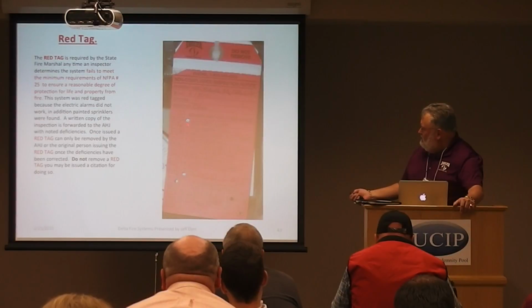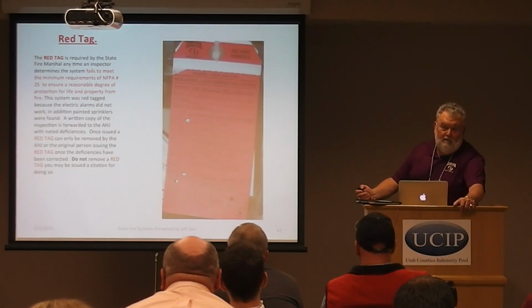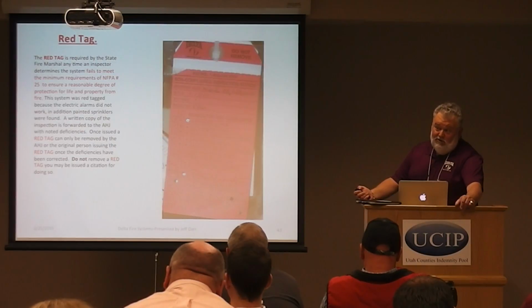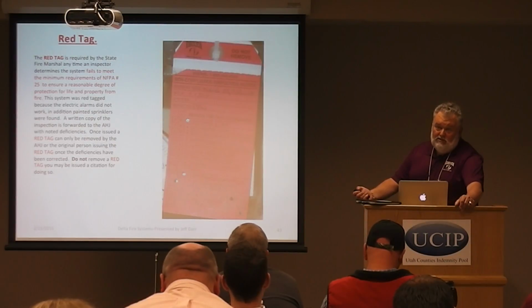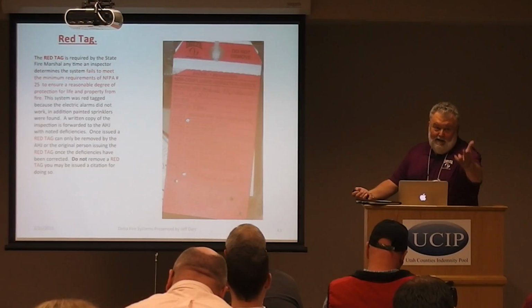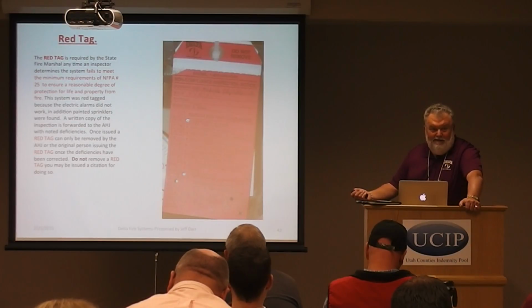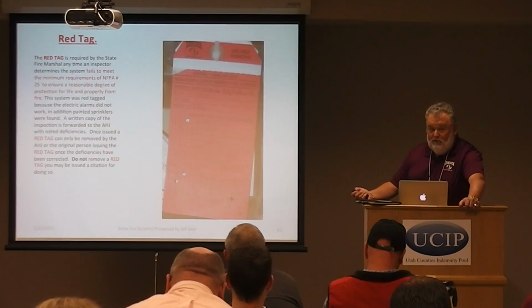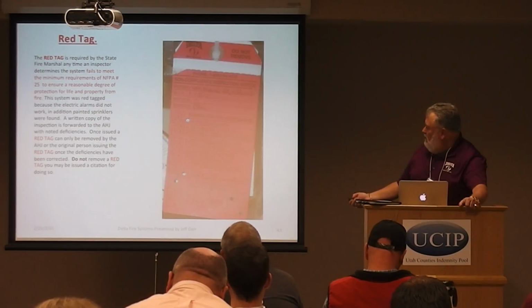This system here was actually red tagged. I don't know if you can see from there, but it's because the alarms were not hooked up and functioning. It doesn't do you a bit of good to have a wet system and have the alarm part of it out, because you're not going to have a bell, you're not going to have notification to anyone. And if I recall the previous presenter, I think that was part of the problems that they had, that they didn't get that early notification. So you want to make sure that that system is going to work.